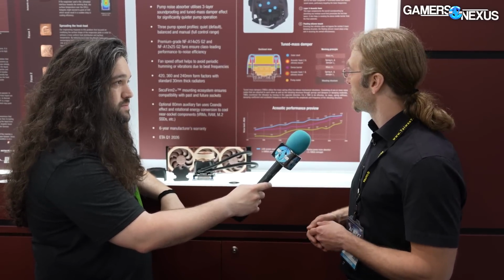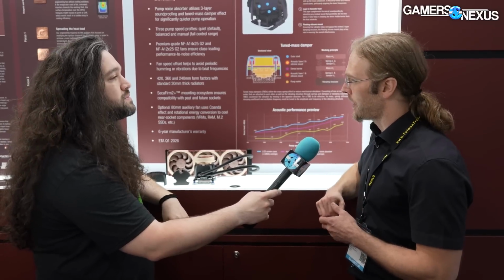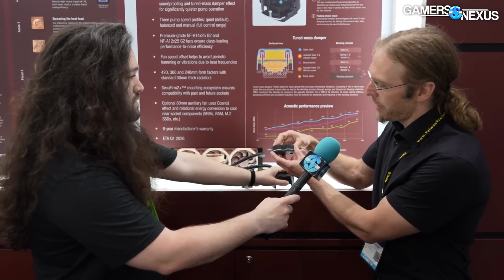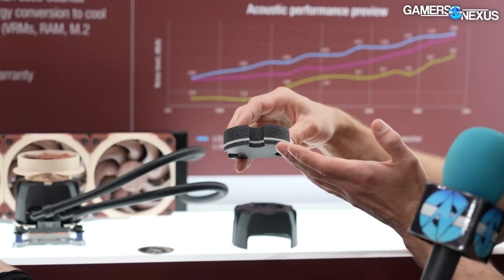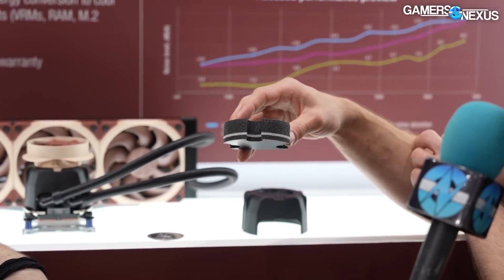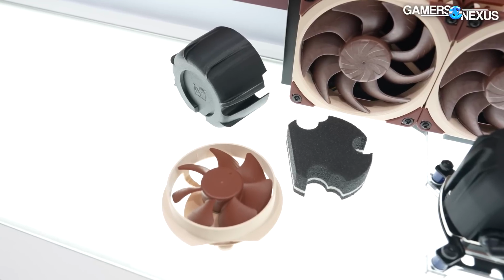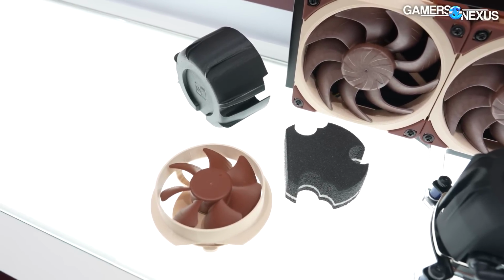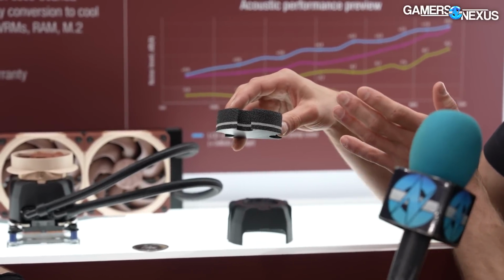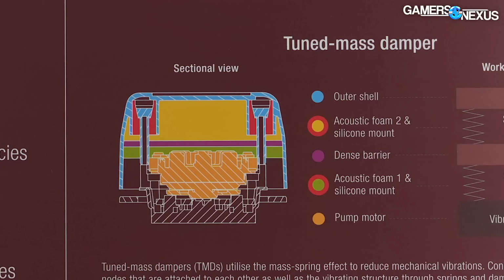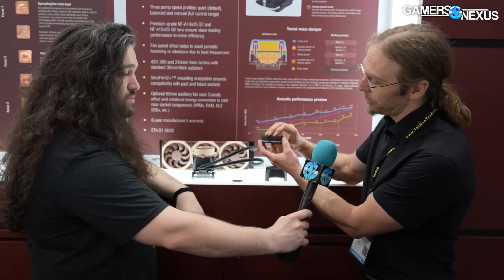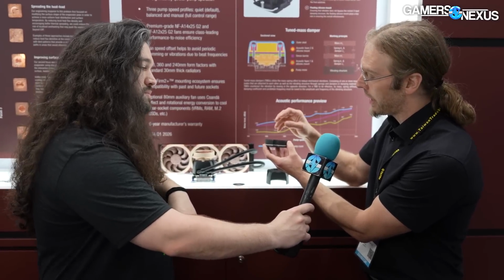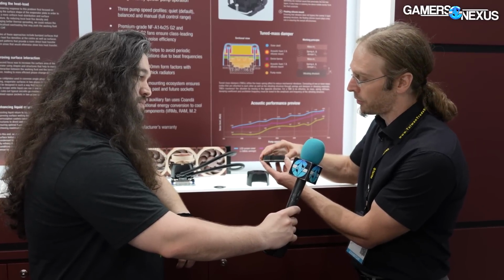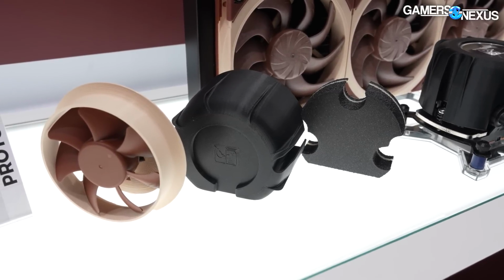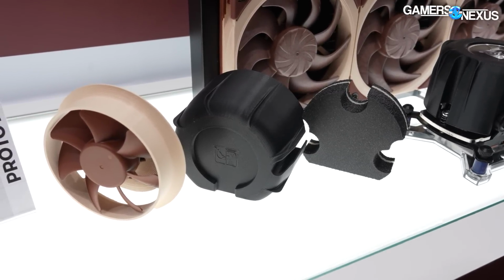The working principle behind it is twofold. On the soundproofing level, we use a 3-layer acoustic foam. So we have two, they are shown in black here, two open pore soft acoustic foam layers and a dense mass barrier in between. The two soft layers help to target high frequency noise, and the mass barrier in between helps to target lower frequency noise. The second thing that the acoustic foam does is that it isolates the hard plastic shell outer cover from a vibration point of view. So it makes sure that no vibrations can be transmitted to that outer cover.